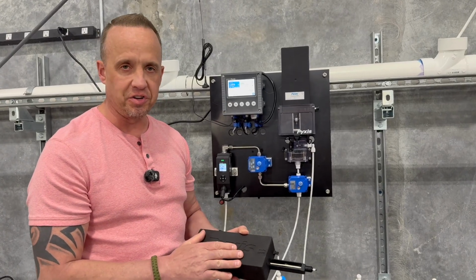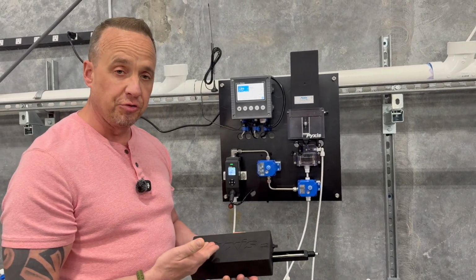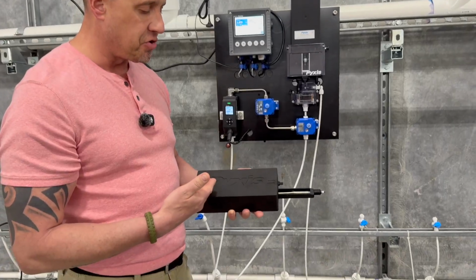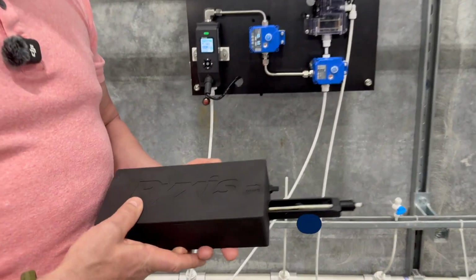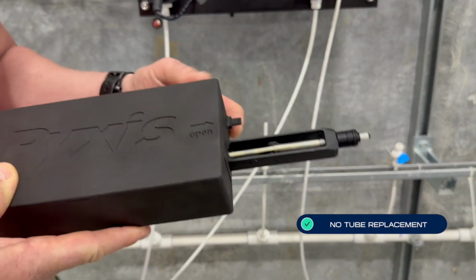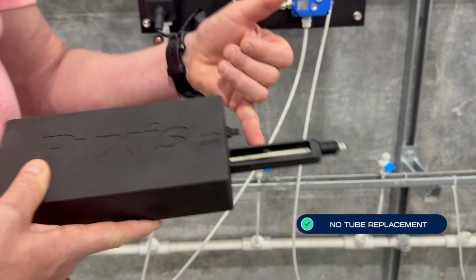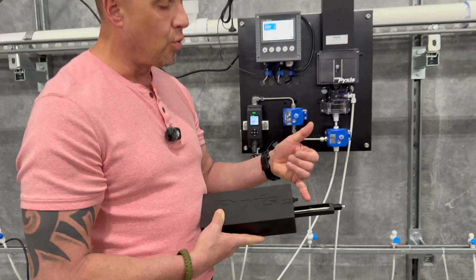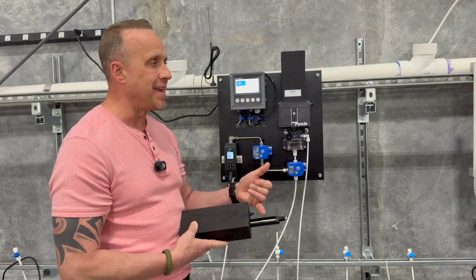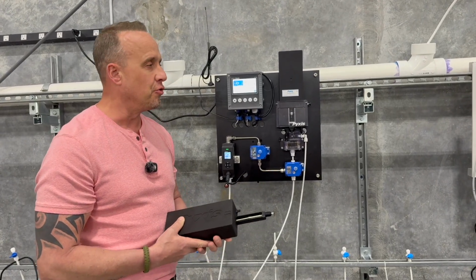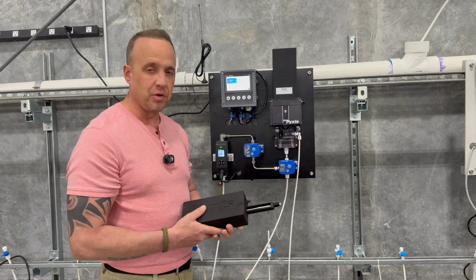What's unique about this platform, as well as the unique flow process to it, is the actual reagent cartridge itself. We've designed a disposable reagent cartridge. The reagent cartridge itself has liquid within it and contains a straight tube, so every time you change the reagent cartridge, you get a brand new distribution tube with the reagent cartridge. So there's no maintenance of peristaltic pumps, there's no replacement of peristaltic tubing to administer the reagent.